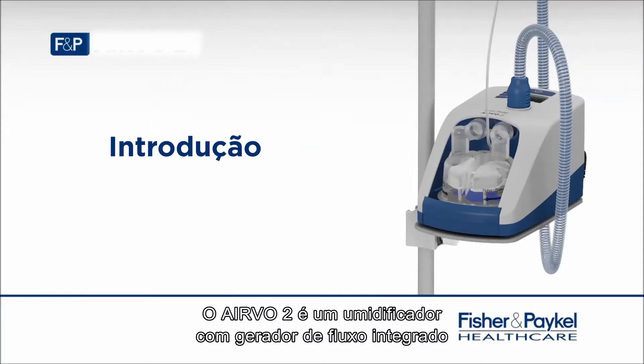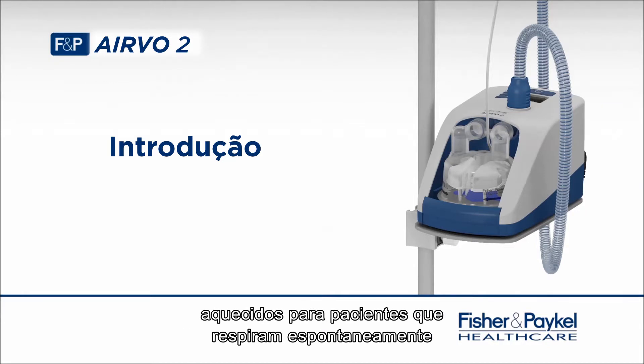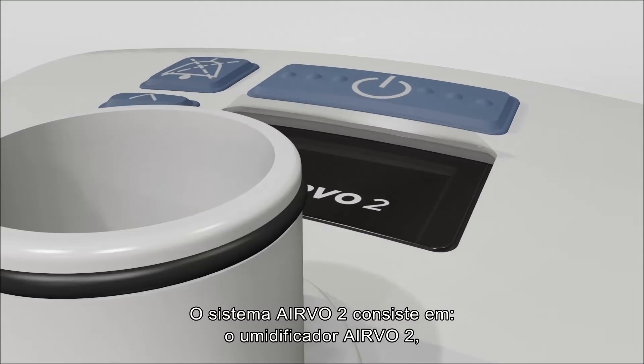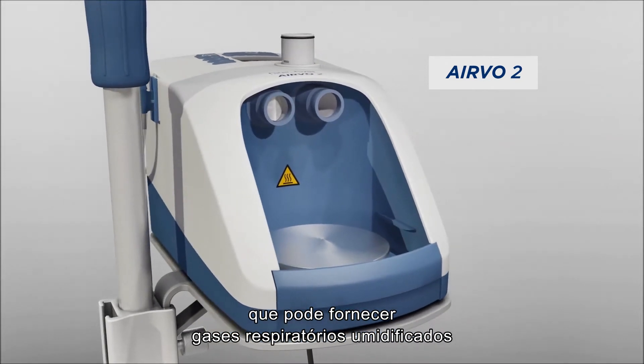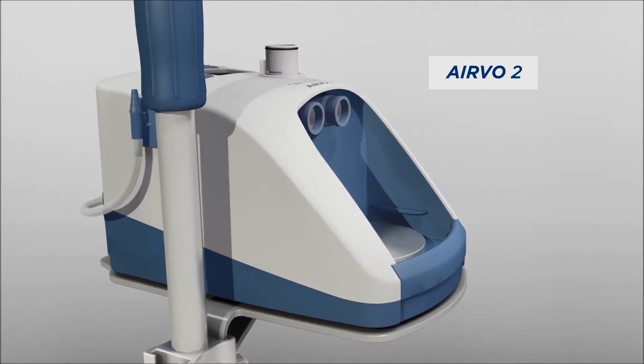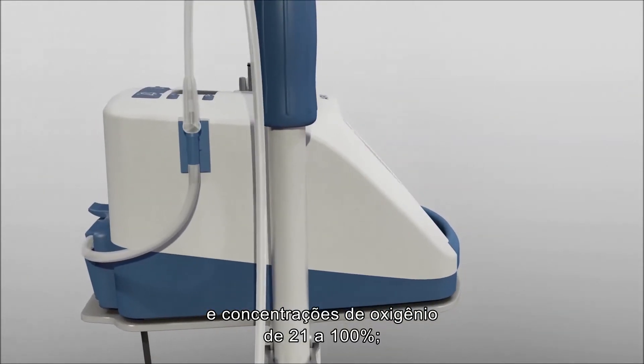The AIRVO 2 is a humidifier with integrated flow generator that can deliver high-flow, warmed and humidified respiratory gases to spontaneously breathing patients through a variety of patient interfaces. The AIRVO 2 system consists of the AIRVO 2 humidifier, which can deliver humidified respiratory gases at flows from 2 to 60 litres per minute and oxygen concentrations from 21 to 100%.